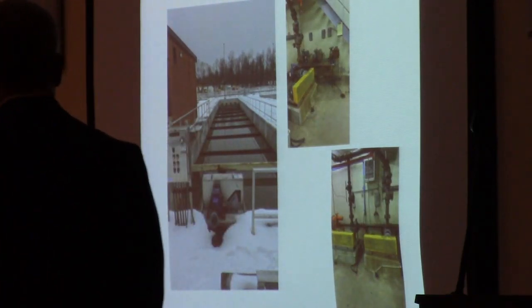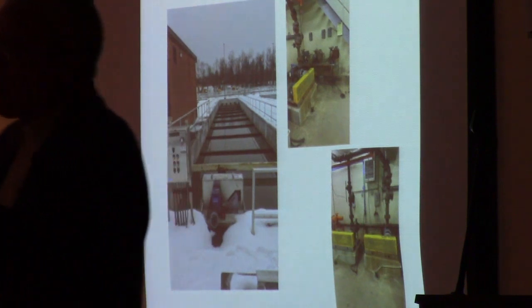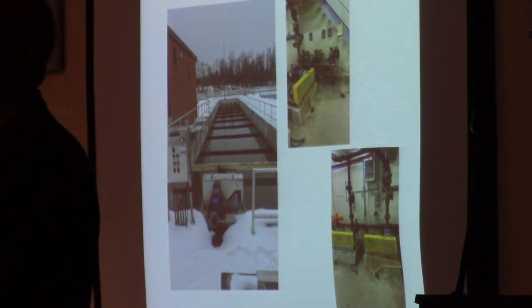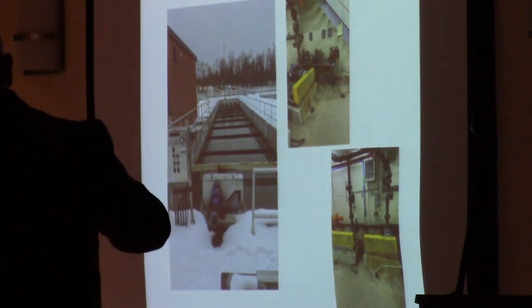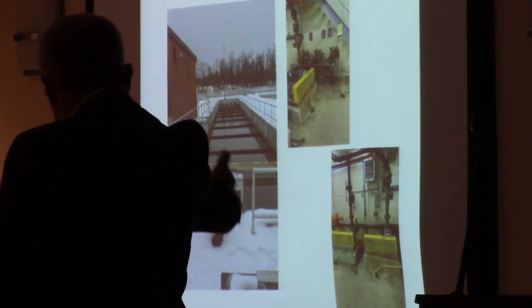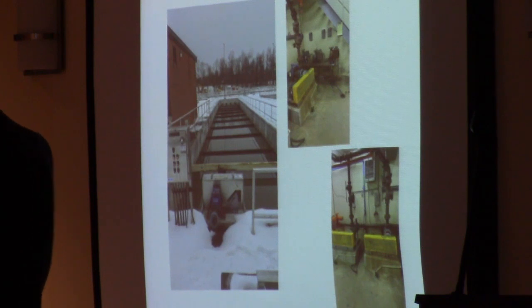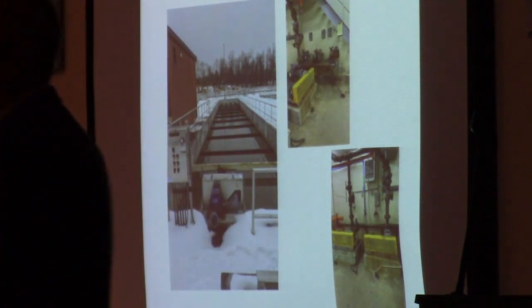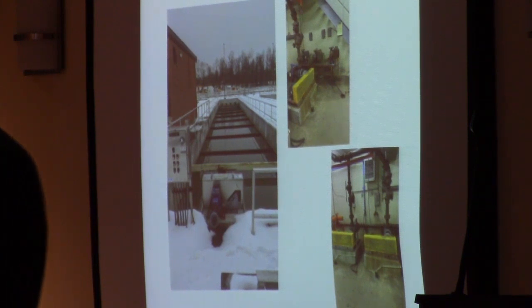The primary clarifiers is the next part of the treatment process. This is where the solids fall out of the wastewater. This slows the flow down, and all of the solids can get removed and pulled and it's sucked out of these tanks with a bunch of pumps. 20, 25, 30-year-old pumps, flow meters, motorized valves that are all outdated, need to be updated.